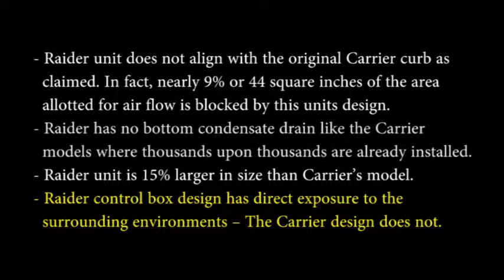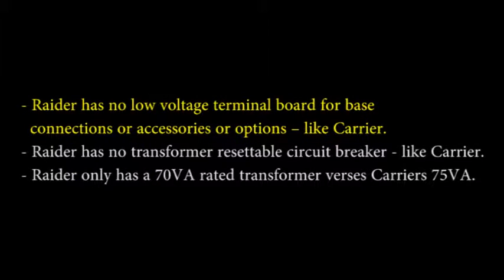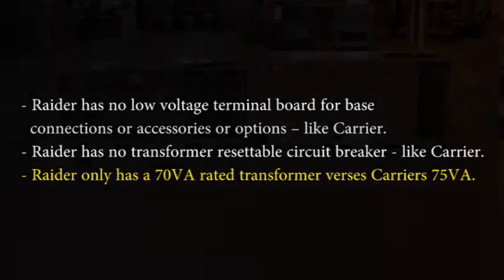Raider control box design has direct exposure to the surrounding environments. The Carrier design does not. Raider has no low voltage terminal board for base connections or accessories or options like Carrier. Raider has no transformer resettable circuit breaker like Carrier. Raider only has a 70 VA rated transformer versus Carrier's 75 VA.